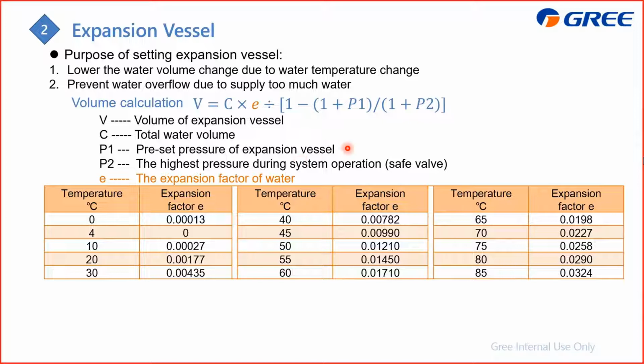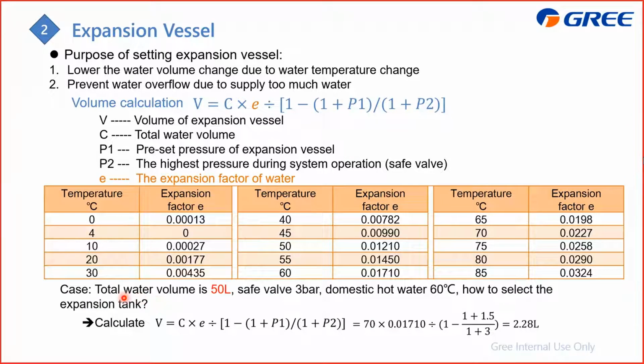A little bit difficult, right? So we give you an example of how to use this one. Let's assume that after you install the water system, the water volume is 50 liters. In that case, if you install the expansion vessel with 3 bar inside, then the domestic water can get to 60 degrees. So that is how you calculate the expansion tank, and from this similar calculation the value can be this one, 2.28 liters.